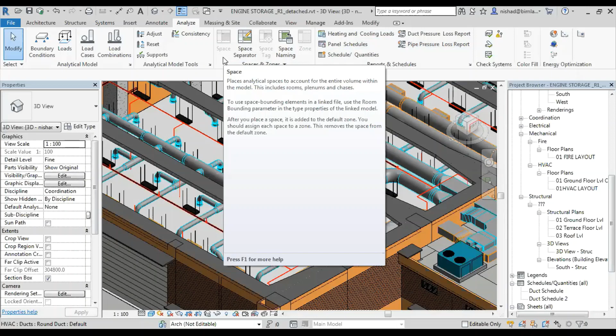So for the heating and cooling load calculation, you need to assign spaces into your building rooms. For the calculation, we need some parameters like location, latitude and longitude, weather conditions, area, volume, sensible heat gain, latent heat gain, occupancy, lighting load, power load, and operating schedule. These are the different parameters for the calculation of the heating and cooling load report of your building.